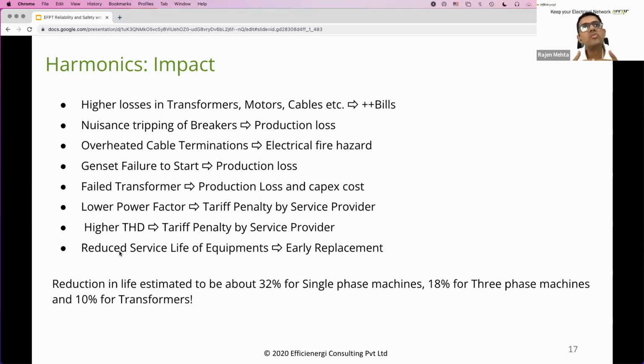Harmonics will cause failures to certain equipment when the voltage distortion, not the current distortion, increases because of a high impedance and very high harmonic currents being generated.